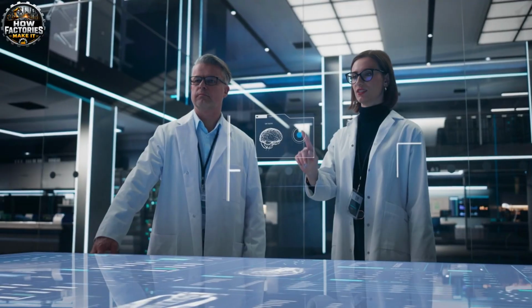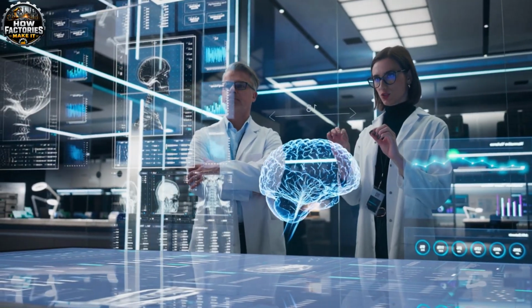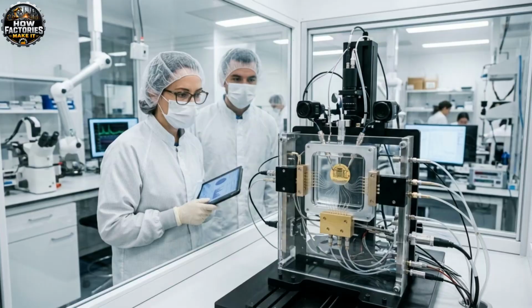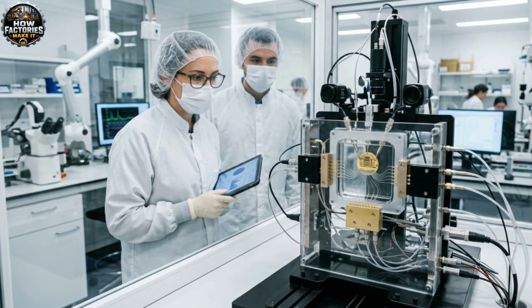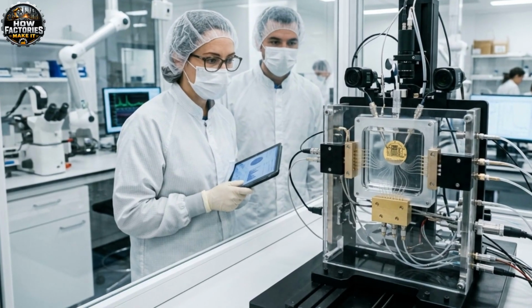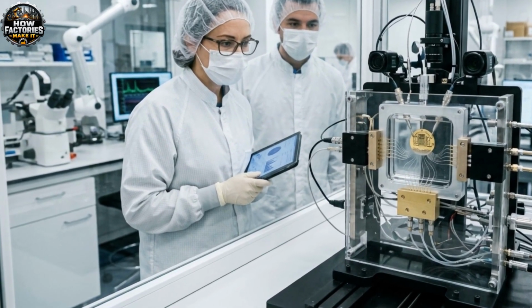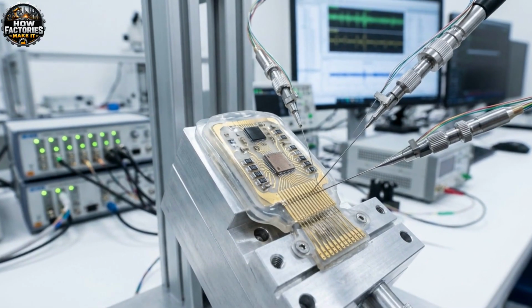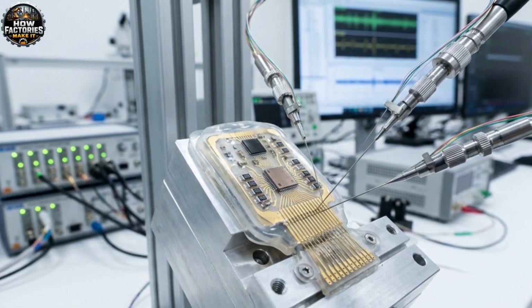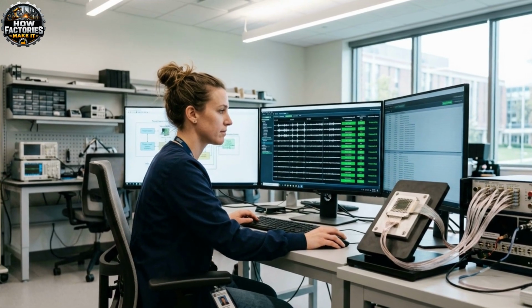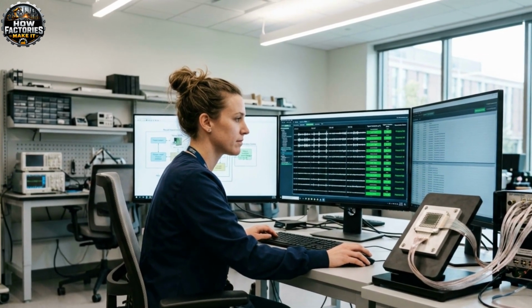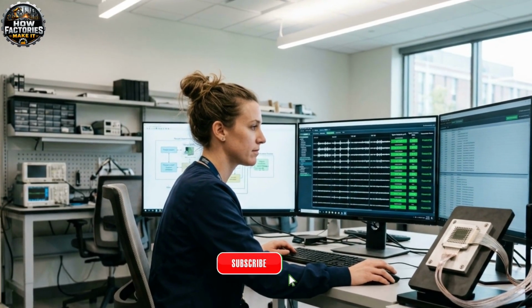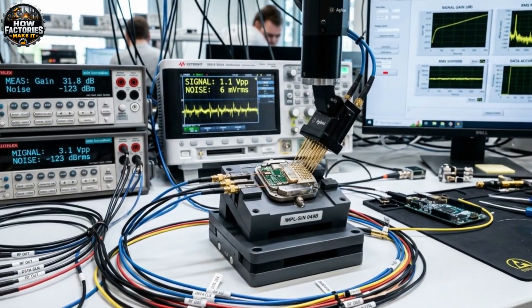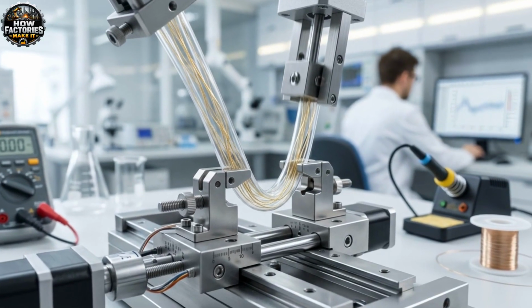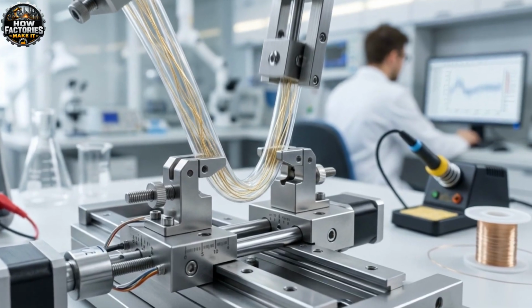Testing an implantable brain interface is far more demanding than testing ordinary consumer electronics. The completed device is placed in an automated test fixture that simulates electrical signals similar to those produced by neurons. Every channel must detect, amplify, and digitize these simulated signals accurately. Engineers measure background noise, signal gain, data loss, processor temperature, wireless stability, and power consumption. The flexible threads undergo mechanical testing. Machines repeatedly bend and move the threads to study how they respond to long-term microscopic motion.